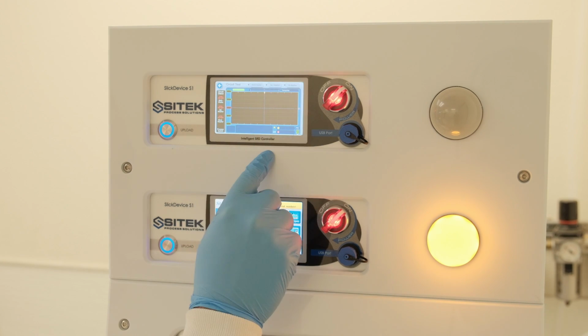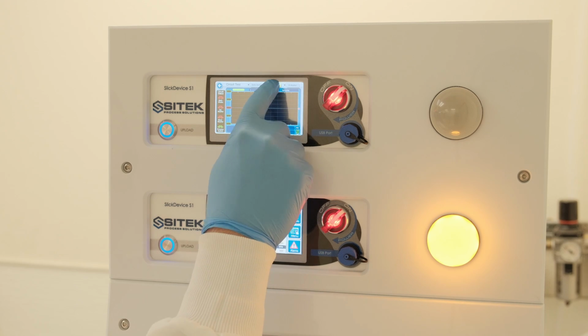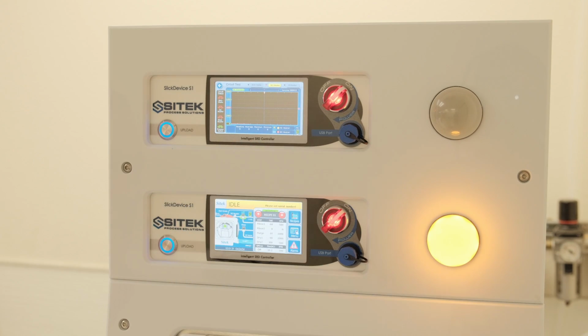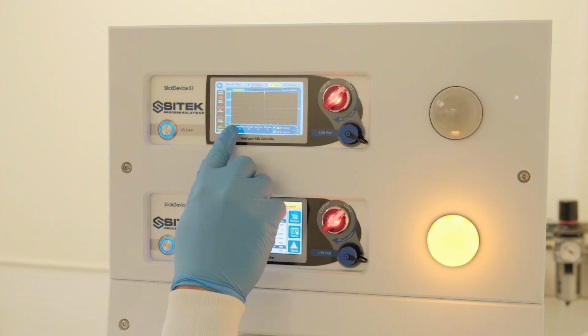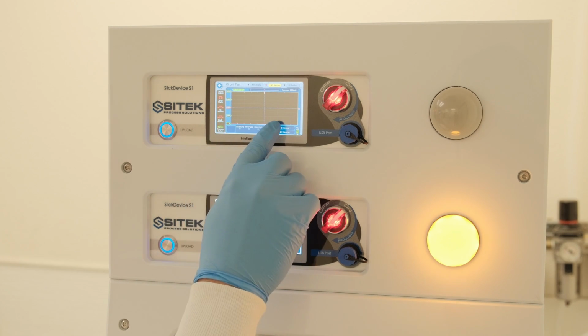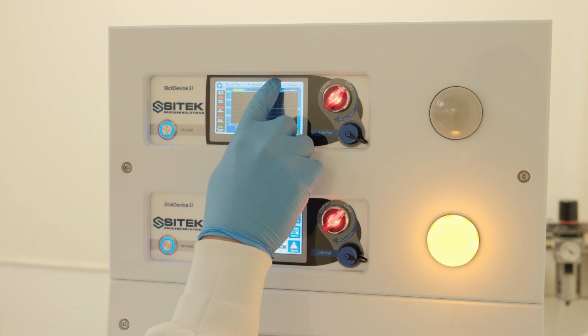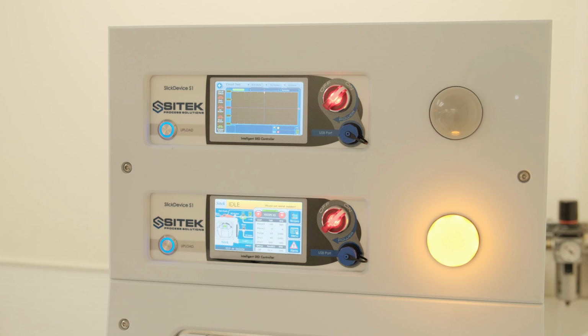So we're going to come to our actuator screen and we're going to try to turn on the N2 heater. And what happens? We see that we can hear the nitrogen blowing, but we have no current consumption at all. So that's really our problem right here. When there's no current consumption, that means we know the heater's not turning on, but we can hear that there's nitrogen flow, and we can also validate that by opening the process chamber and feeling the nitrogen blowing. So now we're going to go take a look at how to troubleshoot this.